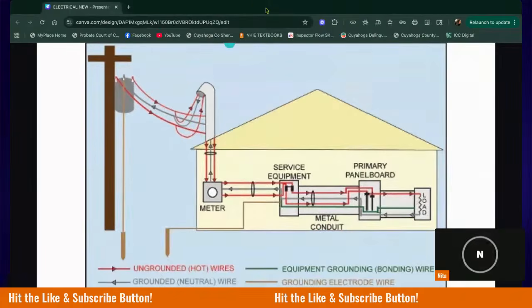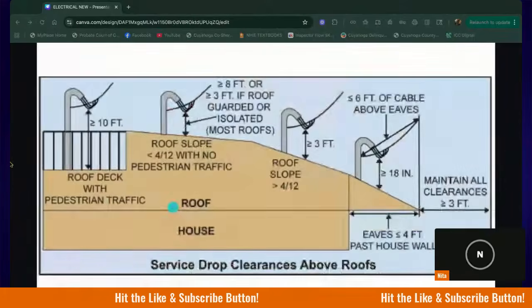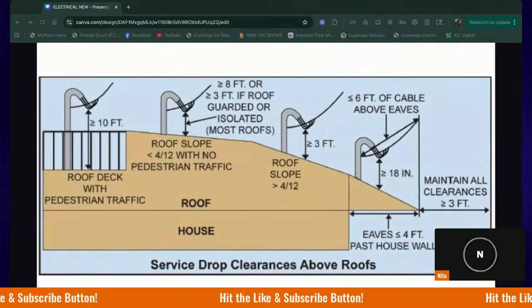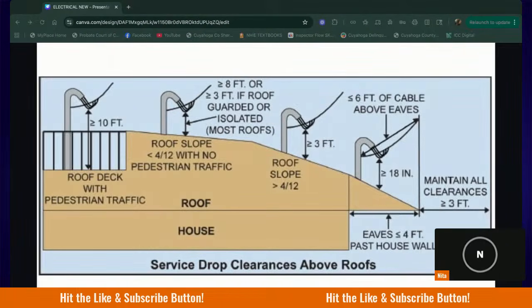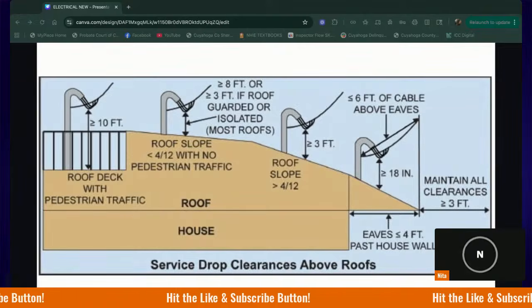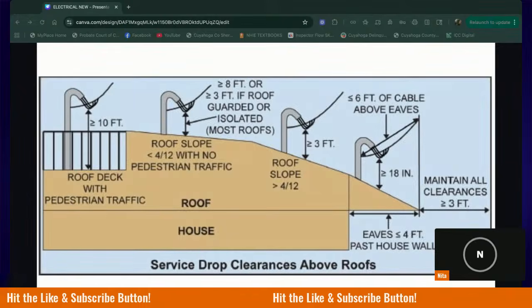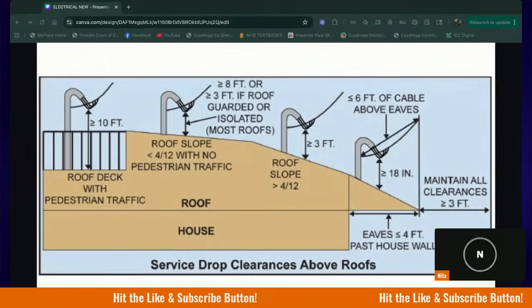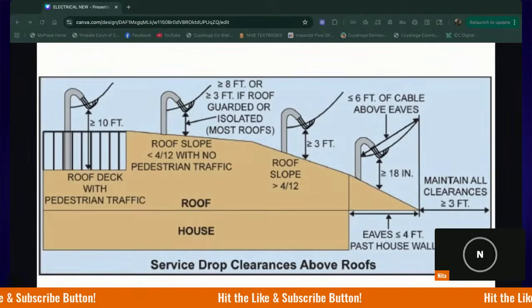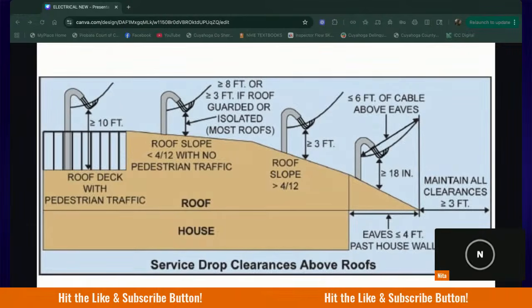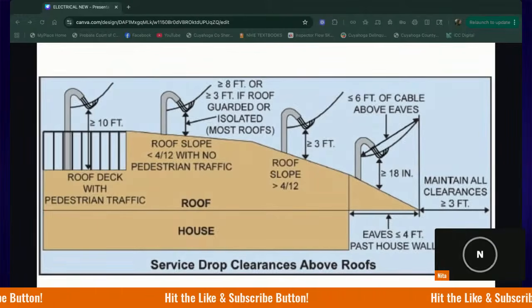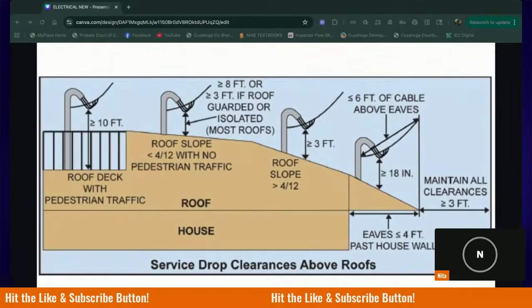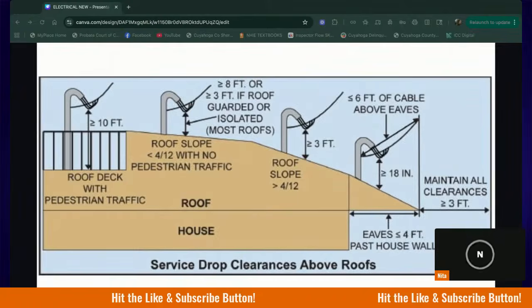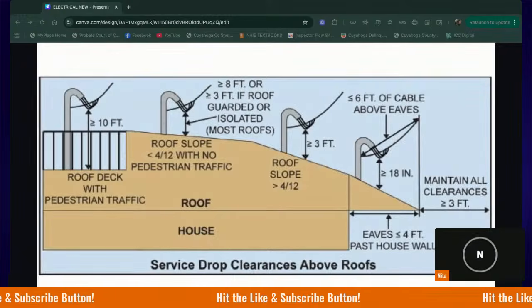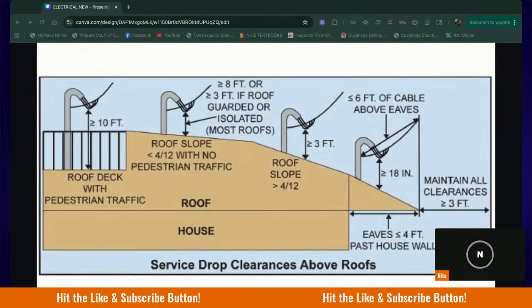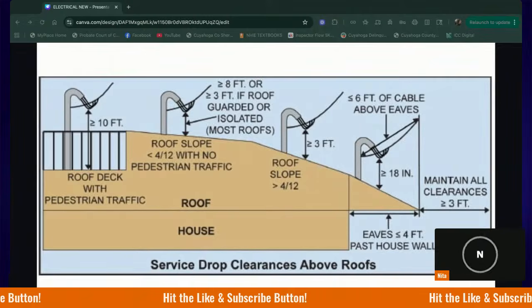Next we need to talk about the clearances. Of course there has to be clearances for our service drop conductors. We want them to have a safe distance over any roofs, decks, walkways, all of that kind of stuff, so that people can't reach or access them. First, a roof deck with pedestrian traffic. If you have some sort of roof area where people can go out and walk on, a deck, a patio, a balcony, something like that, then the minimum clearance is 10 feet above the walking surface for your service conductors. A minimum of 10 feet if there is a roof deck.